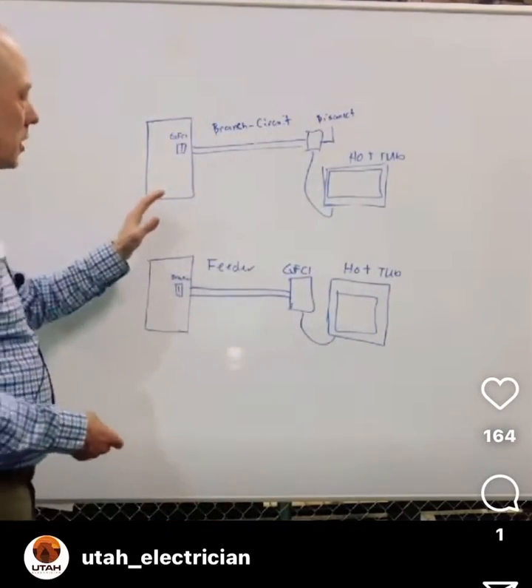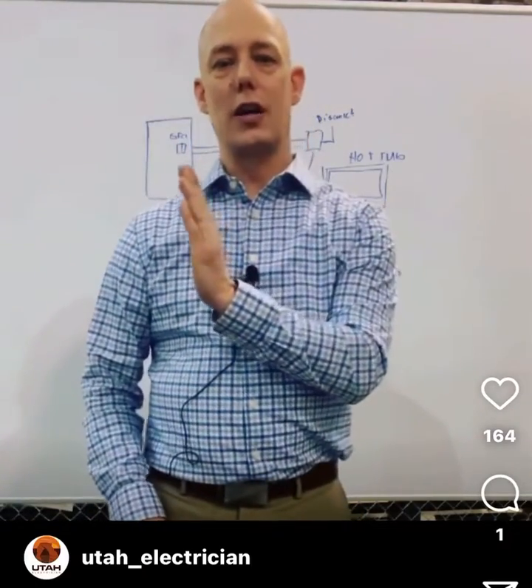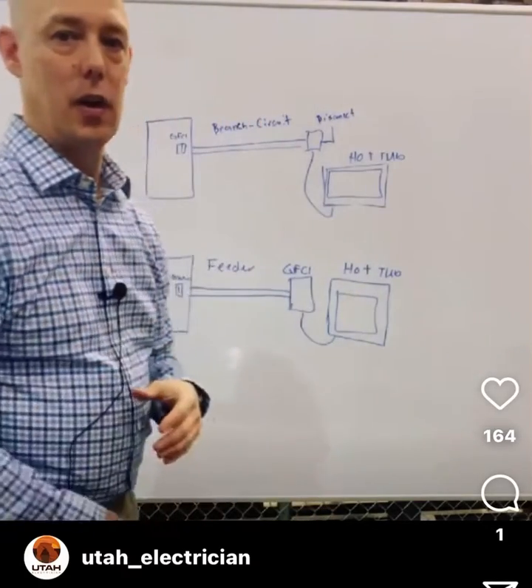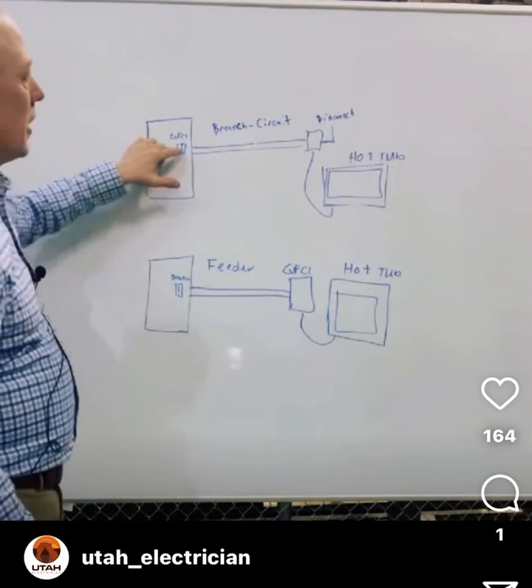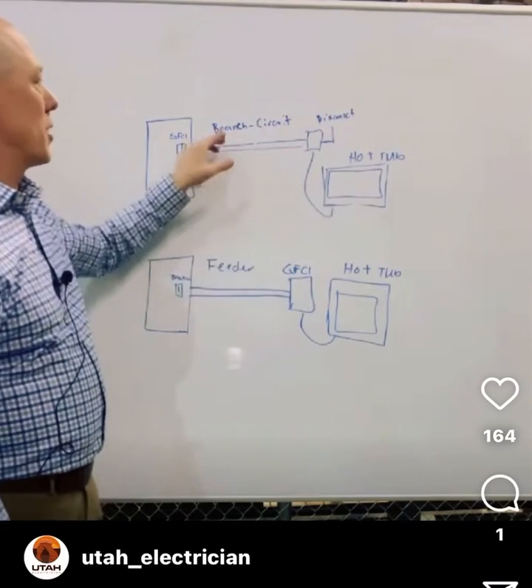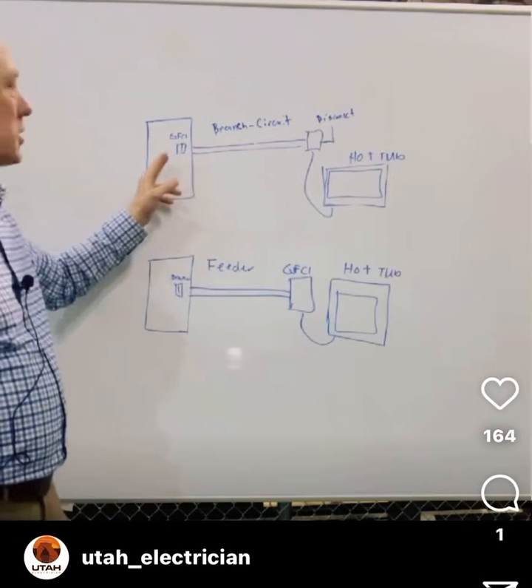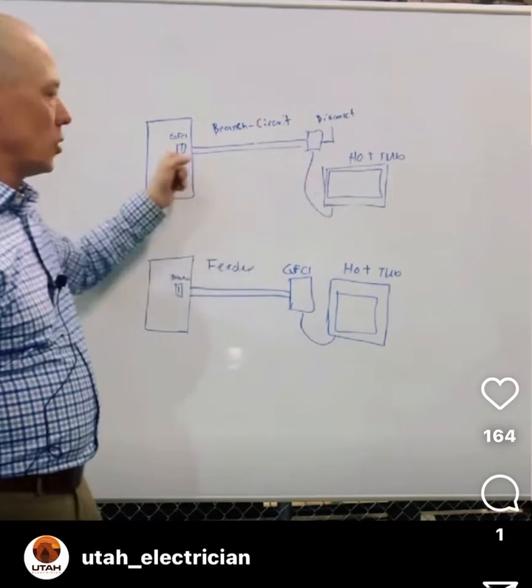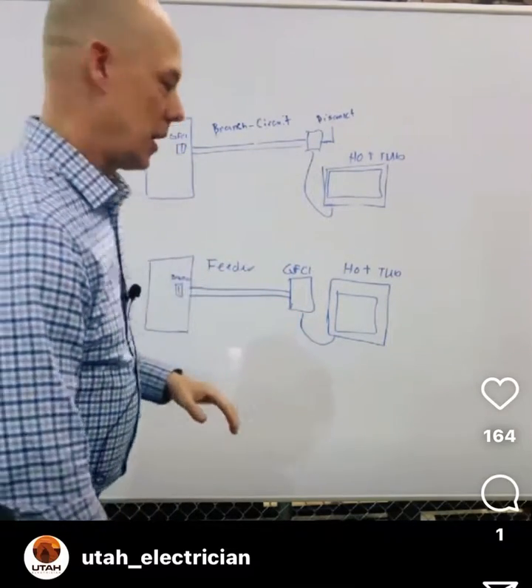So let's look at this one — this is a branch circuit. The definition of a branch circuit is from the last overcurrent protection device to the utilization equipment or the outlet, and I'm paraphrasing that. You see here I've got a GFI breaker, and then it goes to a disconnect, and from there to a hot tub. That makes it a branch circuit because my last overcurrent protection device is here at the sub-panel, so the entire run is on the load side of that overcurrent protection device.